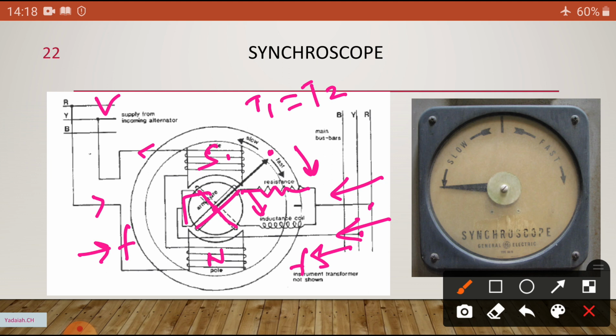If the incoming machine frequency, the speed is more, then it dominates this coil, the torque developed is more, it tries to move the pointer deflecting torque in this direction. So it will show the fast direction, the extreme right, indicating that the incoming alternator rotor is running fast.